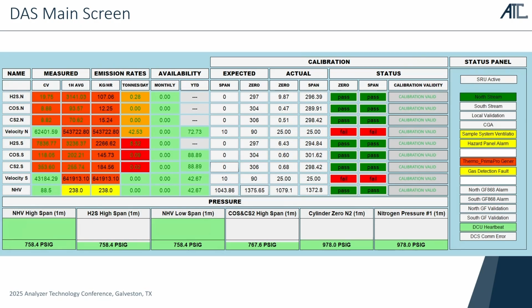It has your real-time data, your 1-hour validated averages, and everything's color-coded. Yellow is like a warning, red is more of an error. Error typically affects data availability, which I'll touch on briefly in the next slide. Then we're calculating the availability, and we also have the calibration validation control. We have the expected values and the actual values that we collect, and you can press the button to change those values, run a calibration, or schedule the calibrations to run automatically daily.